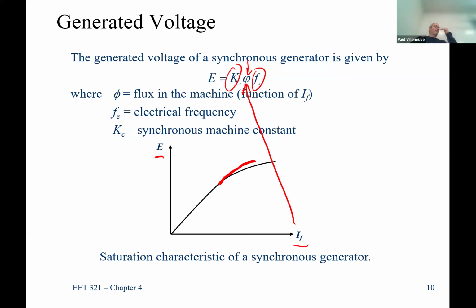Doesn't matter if it's a generator or a transformer, we saw how we got some saturation. And so now we start to saturate, and again, we're going to operate someplace in that region. We're always going to be operating in a saturation region. It's very unlikely that we will ever operate unsaturated unless we're extremely lightly loaded, or the machine is absorbing so much reactive power that we're in the unsaturated region. But here to here is unsaturated, and anything above the knee point would be considered saturated. And that's important to us because the generator has different performance parameters based on whether you're running it in unsaturated or saturated characteristics. And so if you look at, let's see if I can bring up.